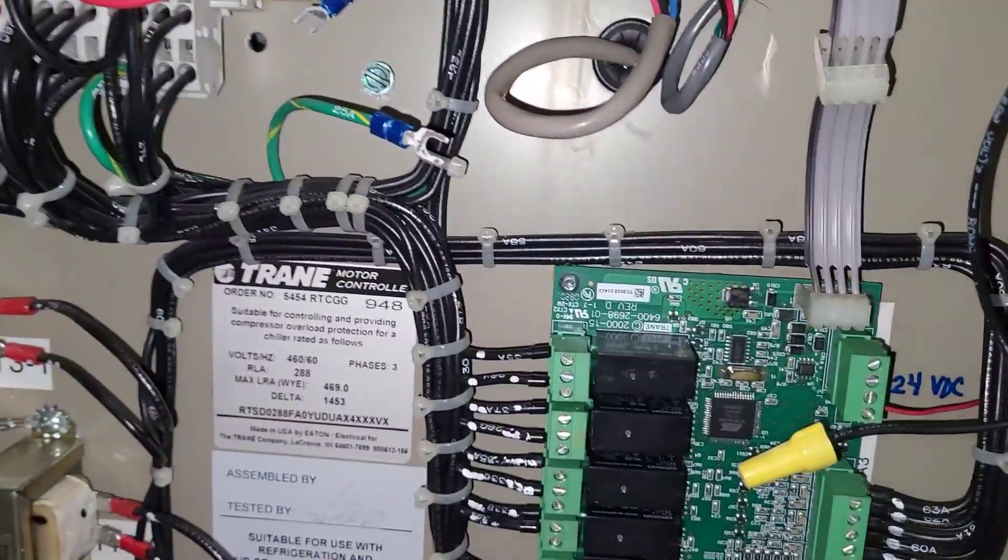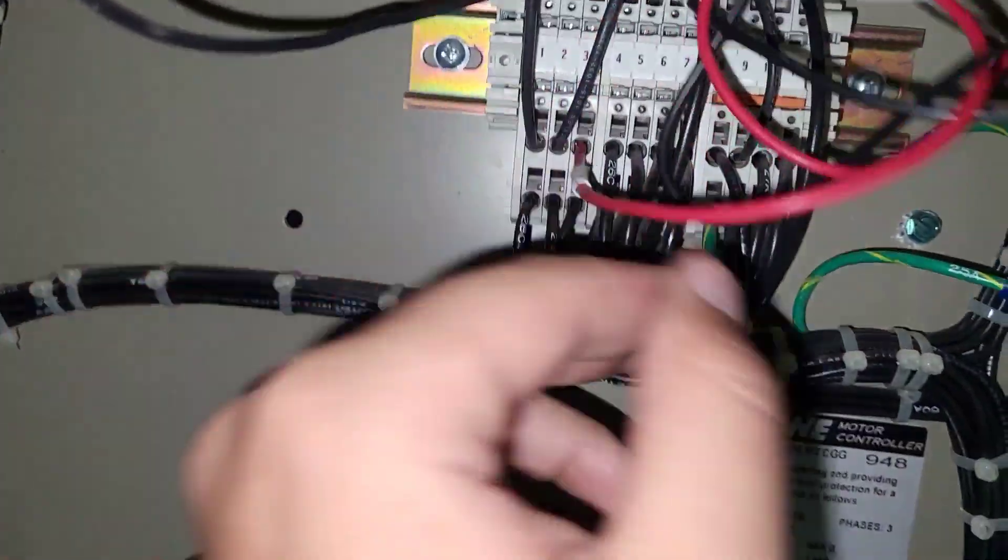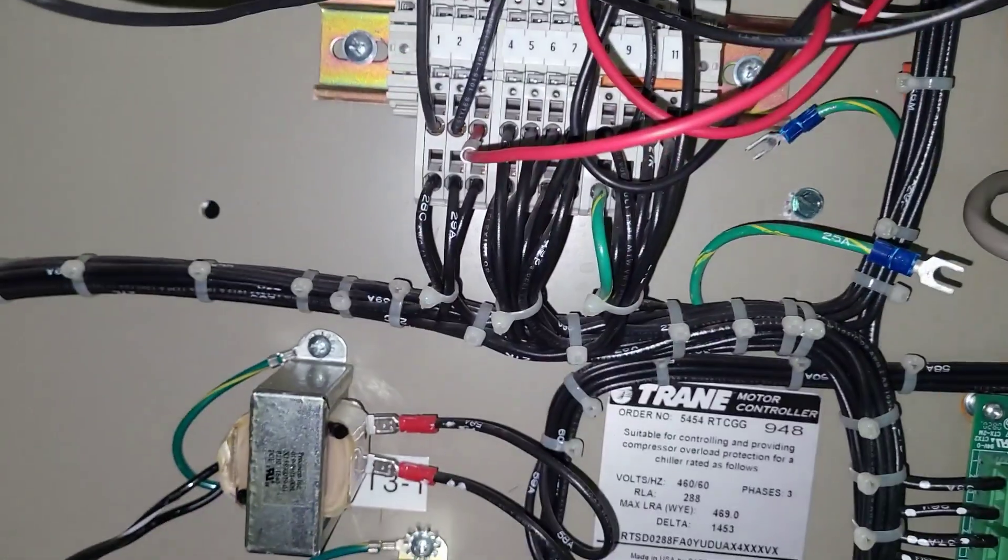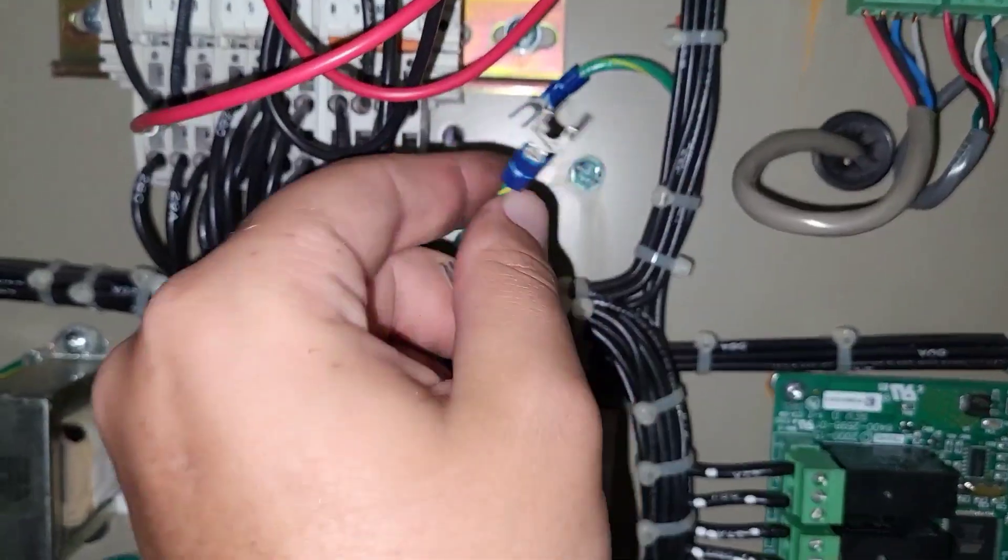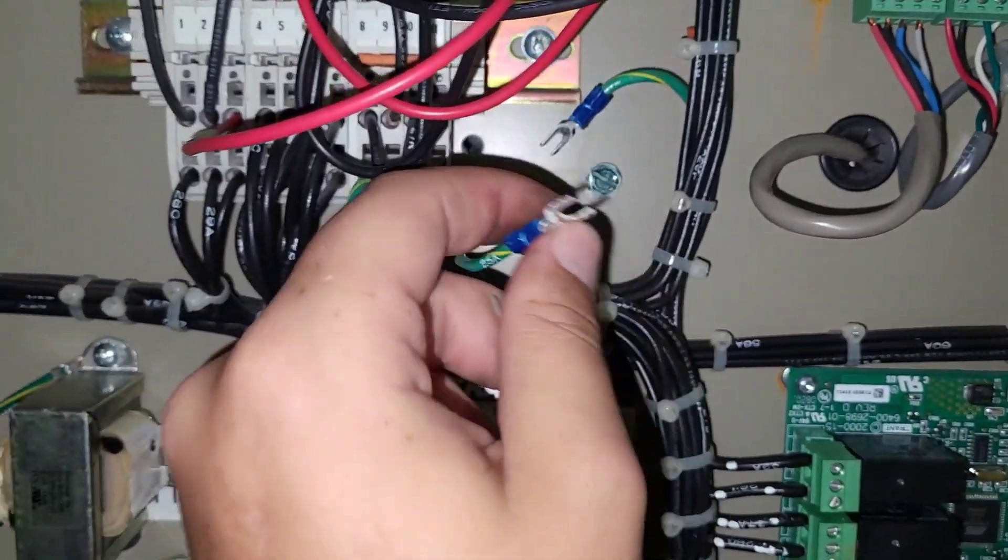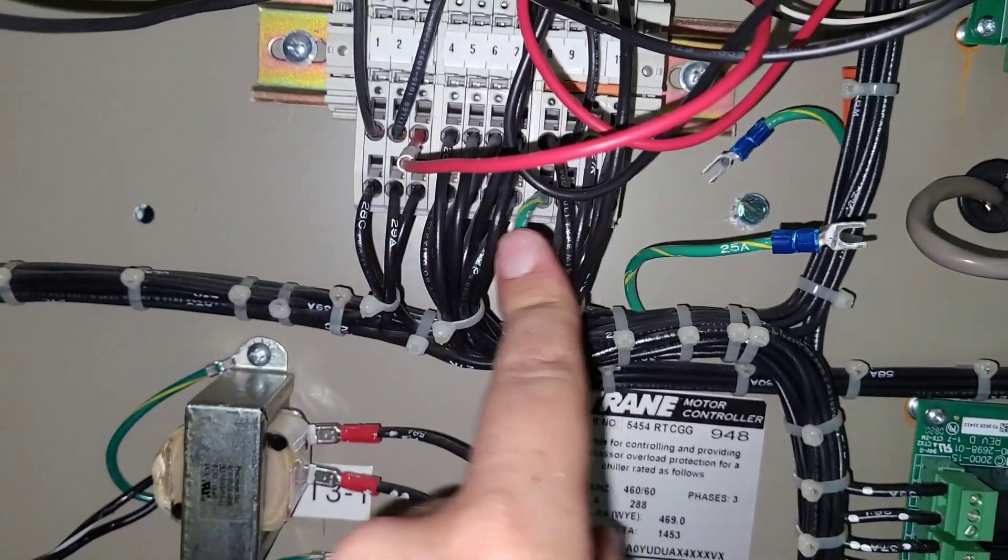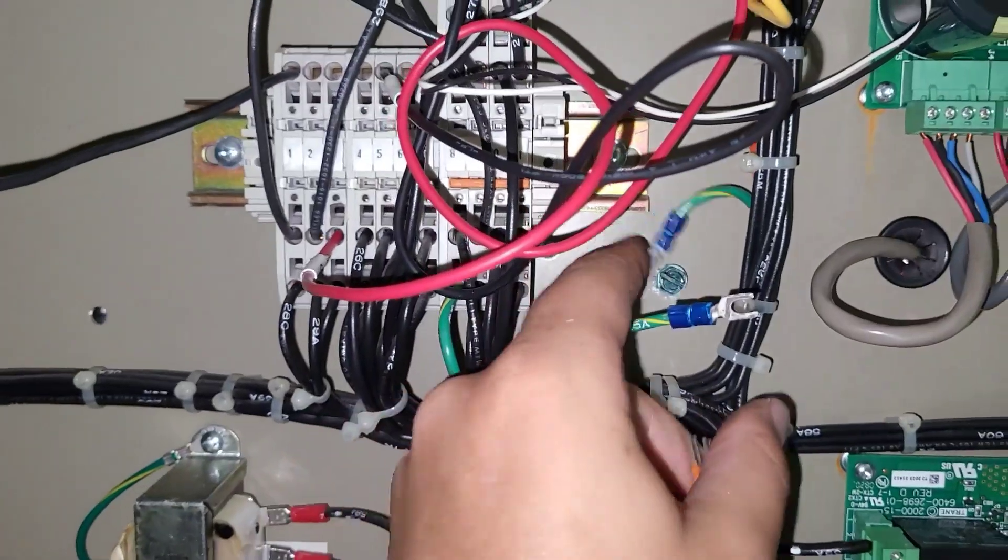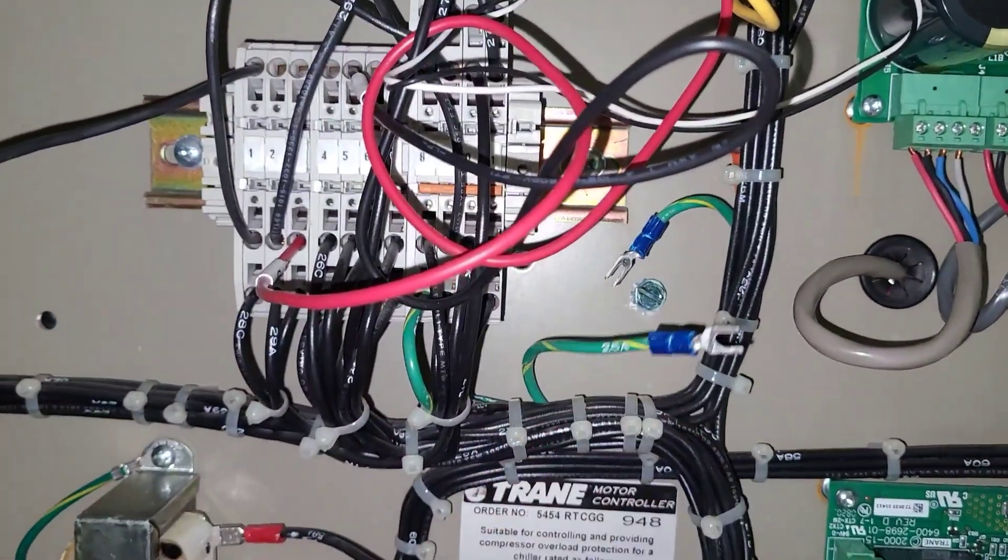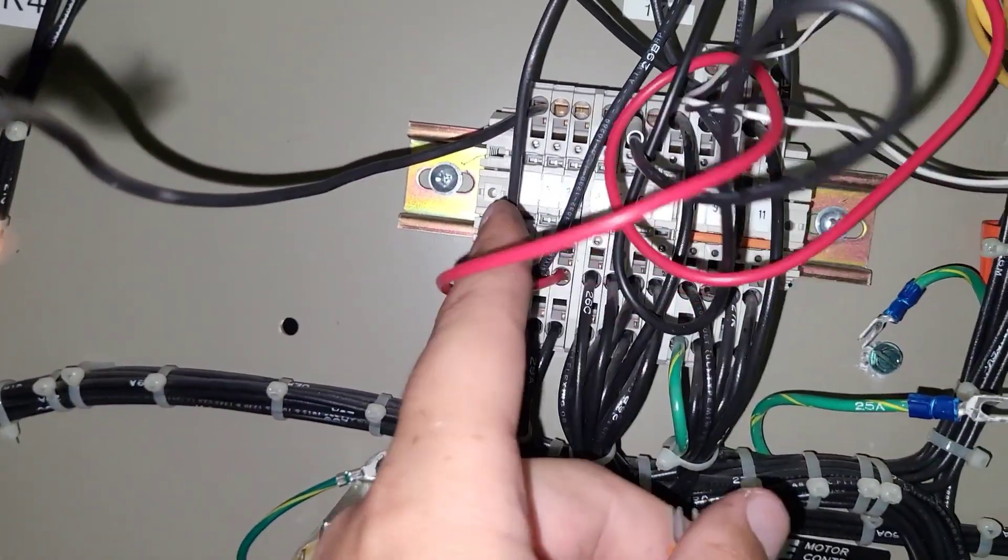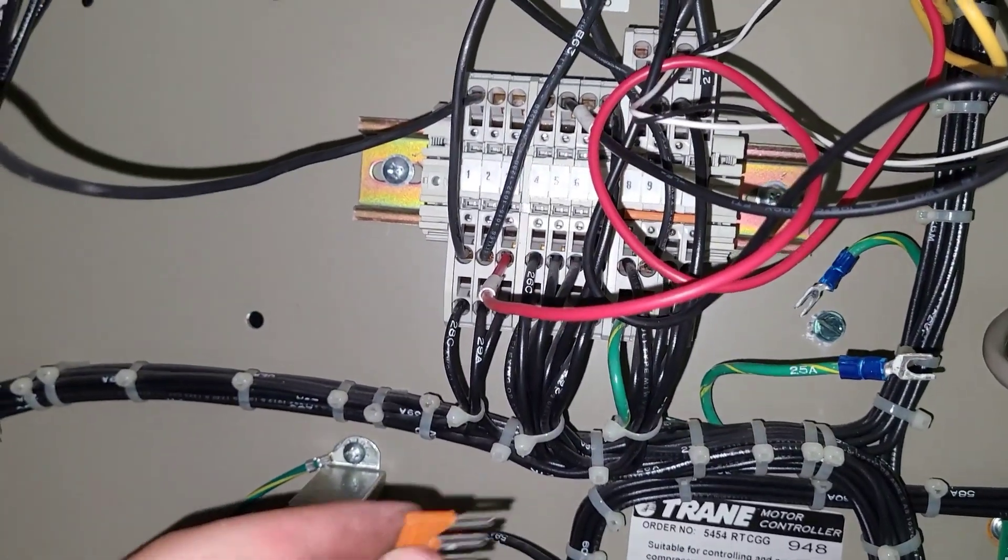One of the things I did was I started checking everything across ground to make sure it all looked okay. Sure enough, one of the things you have to do is you got to pull these ground connections because you'll see everything to ground through the common side on these. If you pull these off, when you see a ground it's a true ground—these aren't actually interfering. Take these off, then I started seeing an actual direct short to ground.